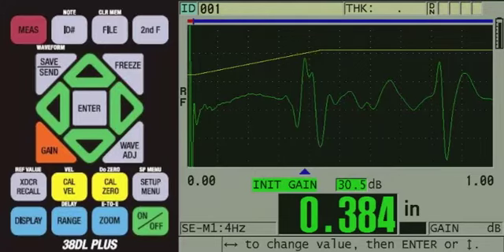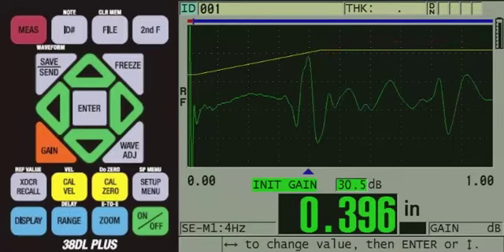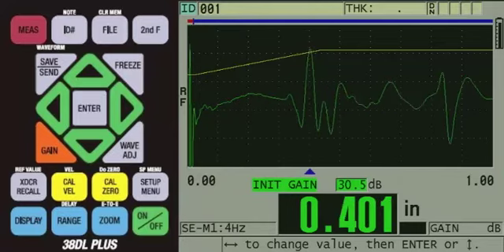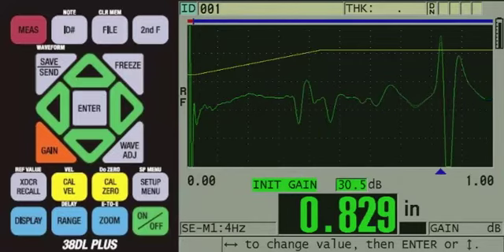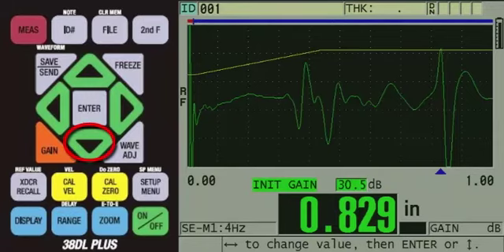The signal appears sooner in time, and although the signal is irregular due to the contour of the steel cords, it does appear positive as we would expect. We can now check the other areas of the sample that include steel cords to make sure the signals are detectable. This steel cord is able to be detected. However, this signal is still too low in amplitude to be detected. Since this signal appears under the slanted portion of the gain line, we will increase the TDG slope slightly.